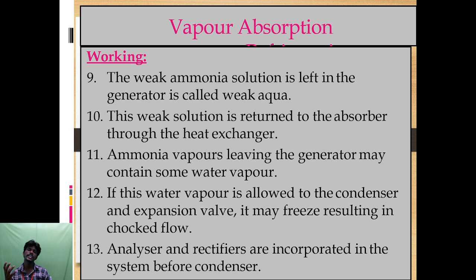If this vapor is allowed to reach the condenser and expansion valve, it may freeze, resulting in choked flow. Analyzer and rectifier are incorporated in the system before the condenser. Then the 14th point: the ammonia vapor from the generator passes through a series of trays in the analyzer, and ammonia is separated from the water vapor. The separated water vapor returns to the generator, then the ammonia vapor passes through the rectifier. I already told that these processes are the same thing.